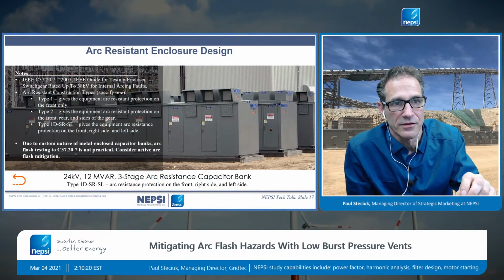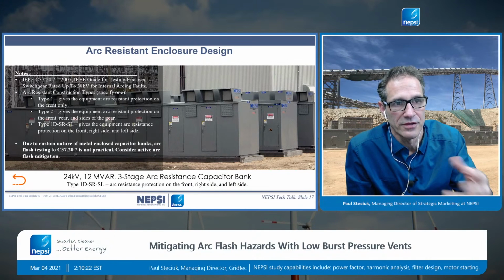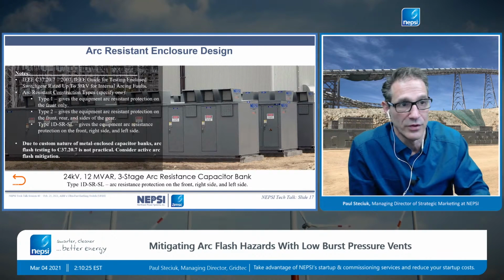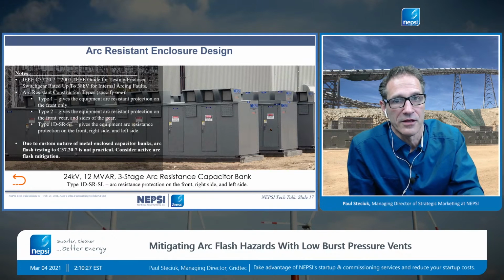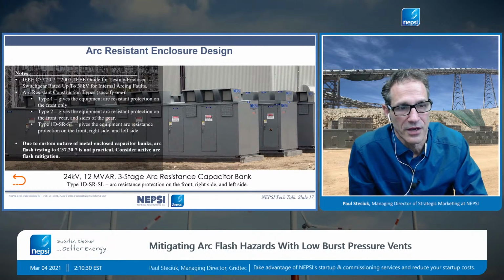The inside volume changes each and every time, which means that we can send one item out to be tested, okay? The next item that we build will be different, and it will be a different inside volume, which means that the test that we did on that one piece of equipment would not apply to the next. So we can say that we're never going to have a certified piece of equipment because it's cost prohibitive. It requires a destructive test. We have to blow it up to show that it can pass the standard C37.20.7.